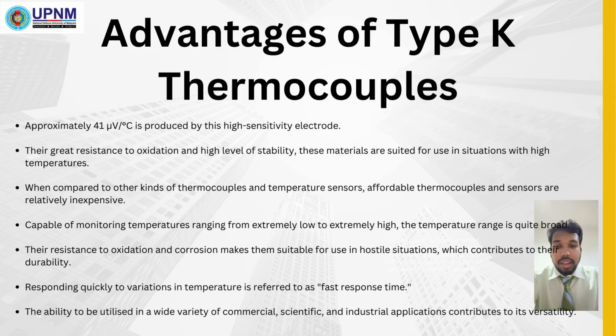Next, we're going to talk about the advantages of type K thermocouple. First of all, it has high sensitivity. It generates around 41 microvolt per degree Celsius, which indicates high sensitivity to temperature changes. The second one, it has high temperature stability, which is suitable for application in high temperature environments. The third one is cost effective compared to the other sensors. The fourth one, it has wide temperature ranges.